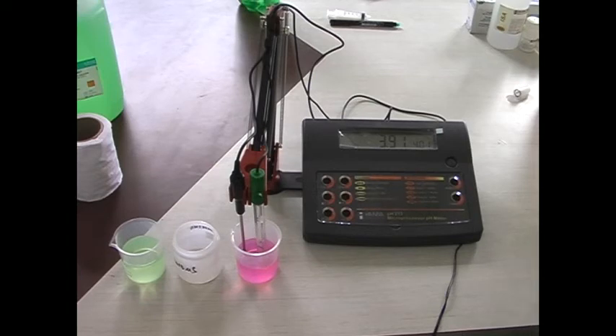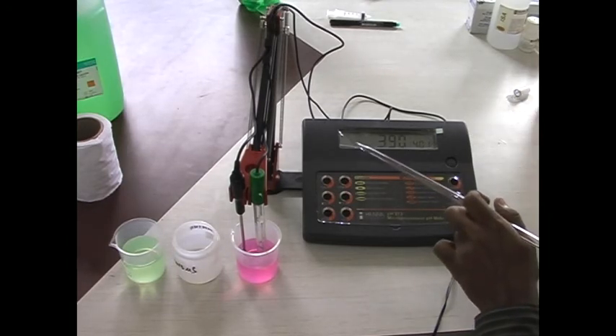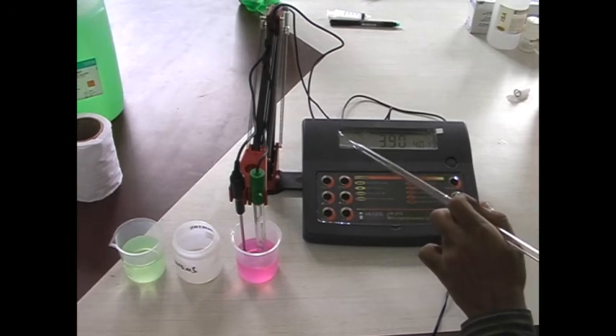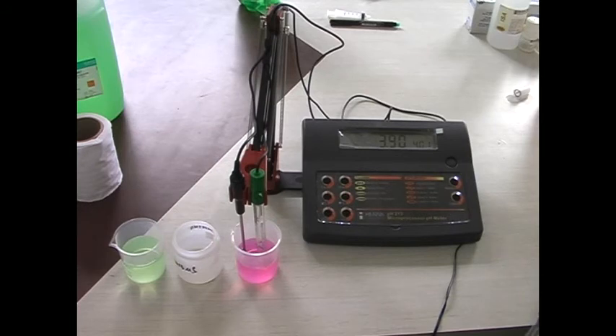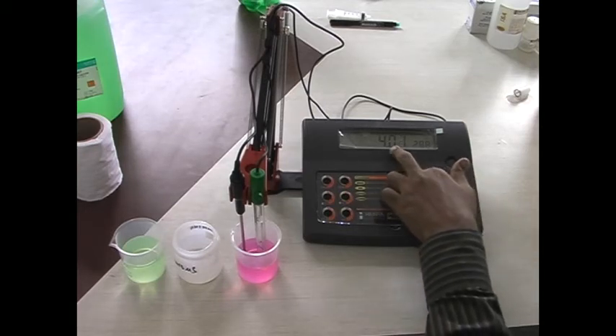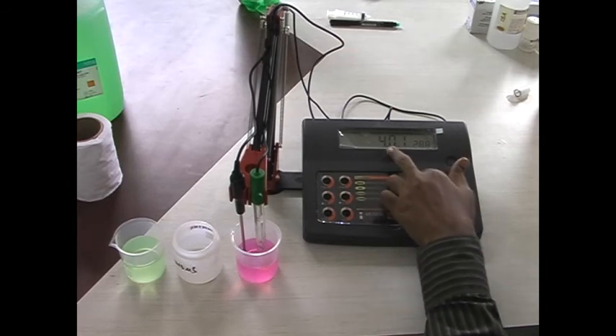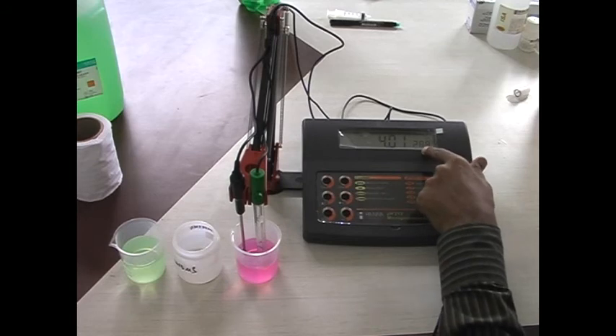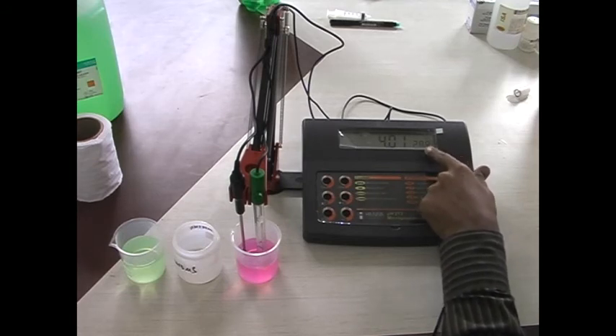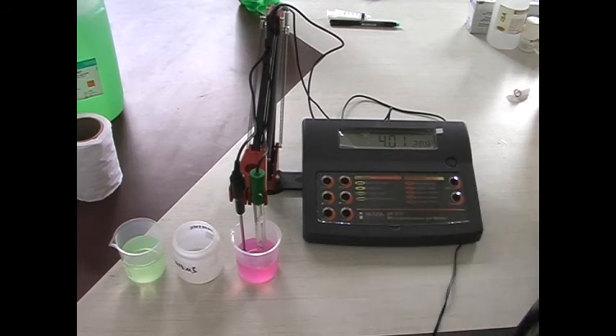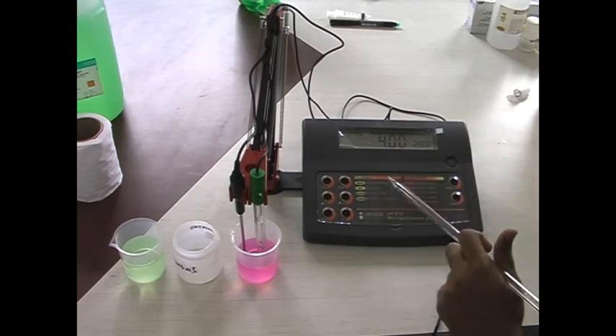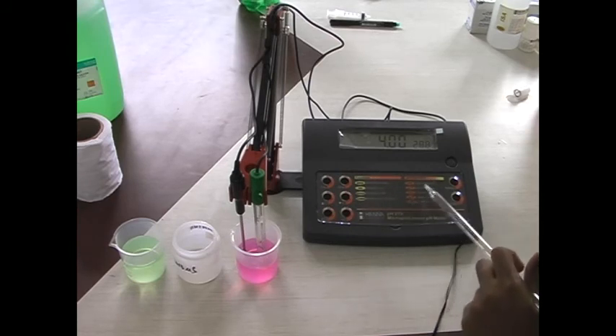If you want to calibrate your meter for 10 pH or 6.86 pH, you can do that calibration. Now you can see the instrument is showing CFM and the ready on this left side of the display. So at that time you just press confirm. Now the instrument will store the calibration. Now the instrument is calibrated. This is the actual value that the instrument is showing. This is 4.01 and this one is temperature, that is 28.8 degrees Celsius. So this is the calibration procedure. This calibration procedure you can find on the front panel of the display. It is written step by step.